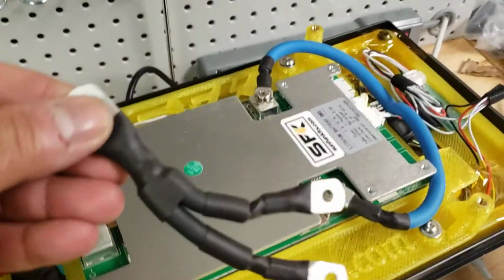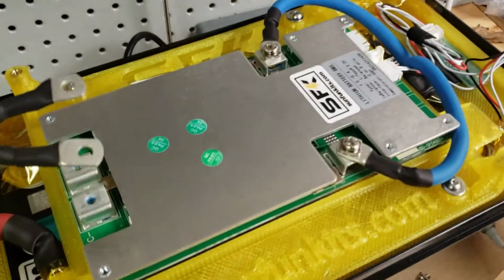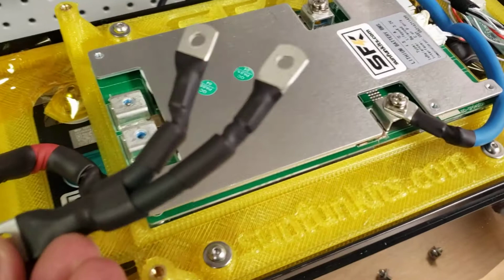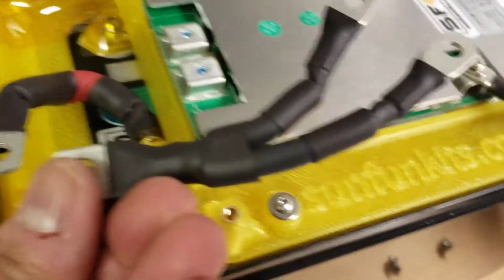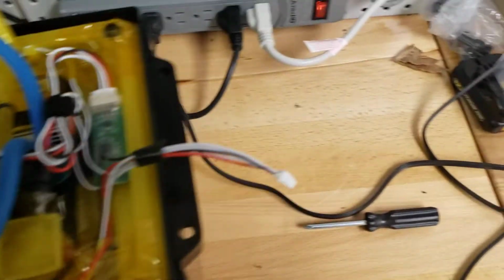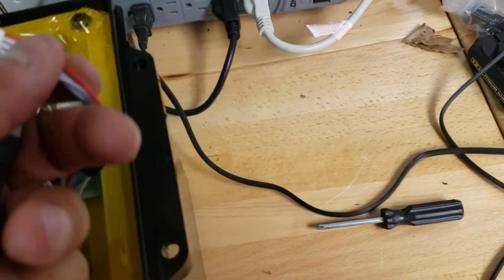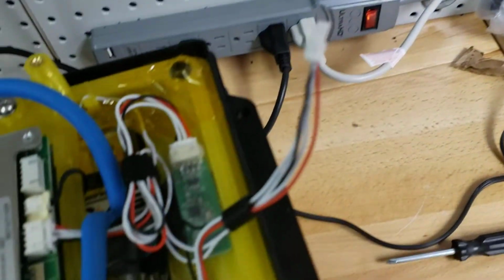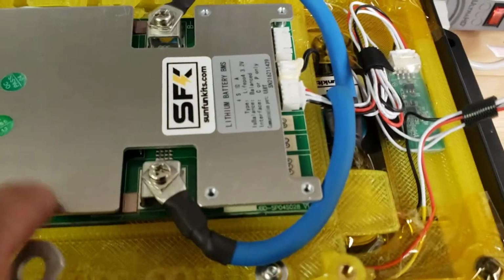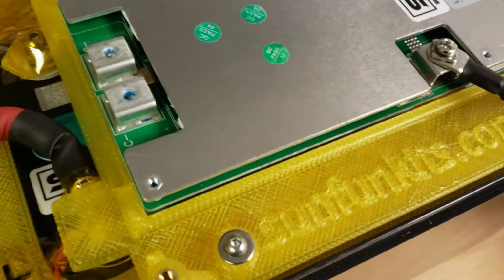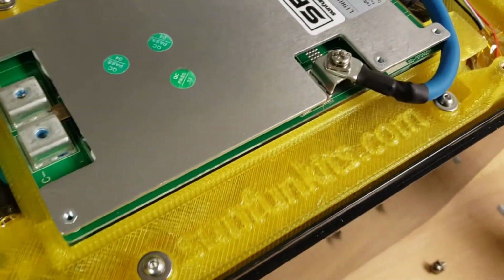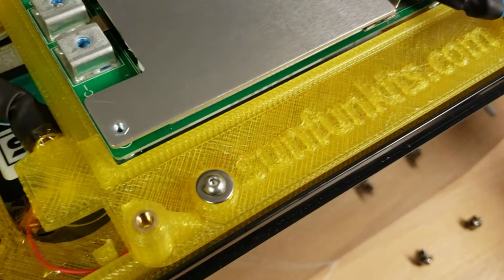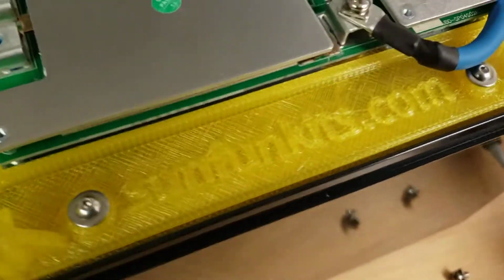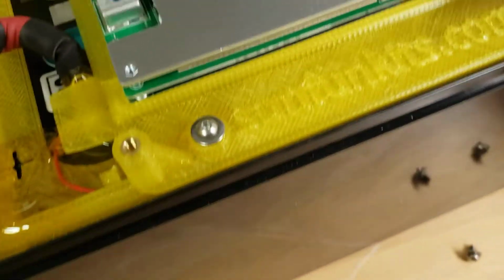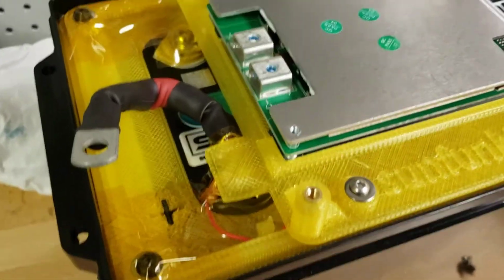As for the second terminal, this is the negative terminal. You obviously want to make sure you don't arc these two, and one way to prevent that is by keeping the balance lead disconnected during install - this ensures your BMS is disabled so there's no current flowing through. We'll install this last thing, then proceed to putting the top on, which will complete our battery and it'll be ready for testing.